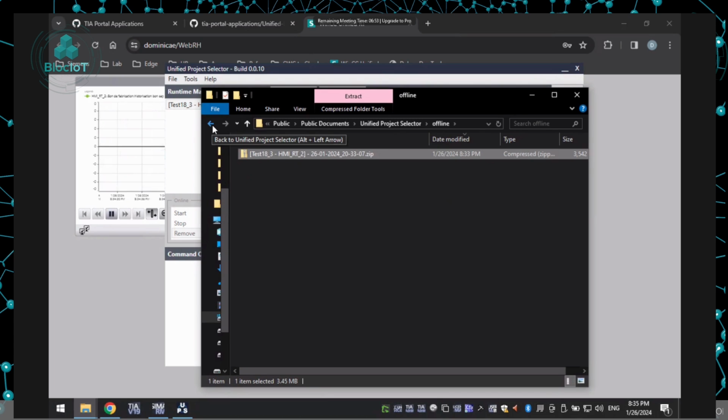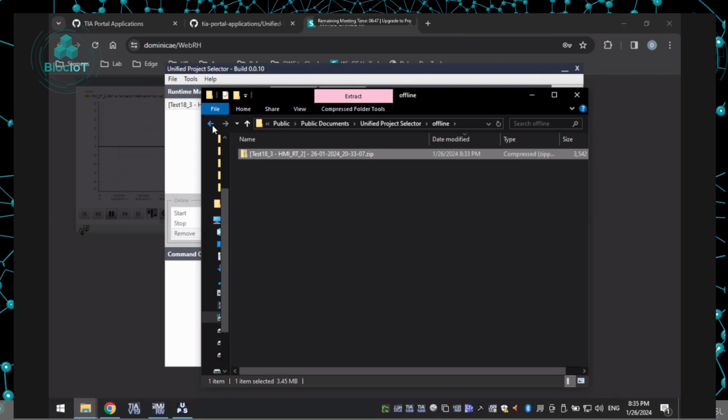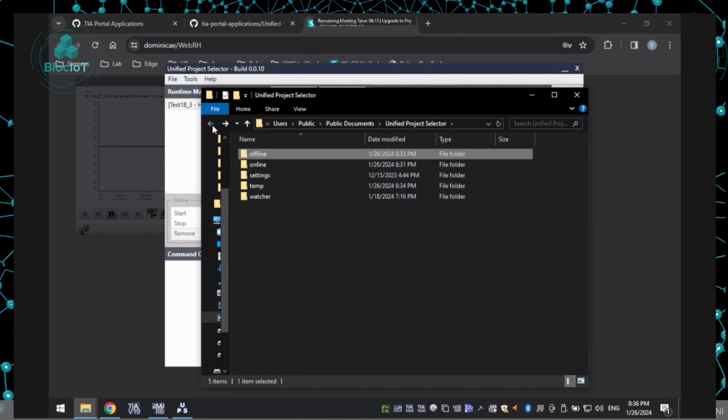By the way, I said it will not keep the databases, but it will recreate them. So it won't back up your database, but of course, everything that requires a database will be recreated and will work. So if you were archiving a value, the tool will not back up for you the archived values acquired up to that time, but it will start recreating those archives. So if you know how to back up your database and just put it on the new system, then you're good to go. Everything's backed up.